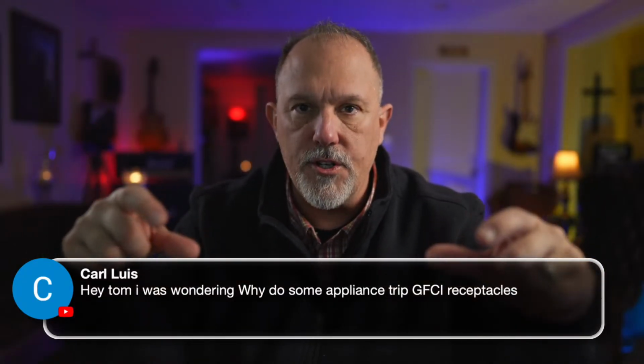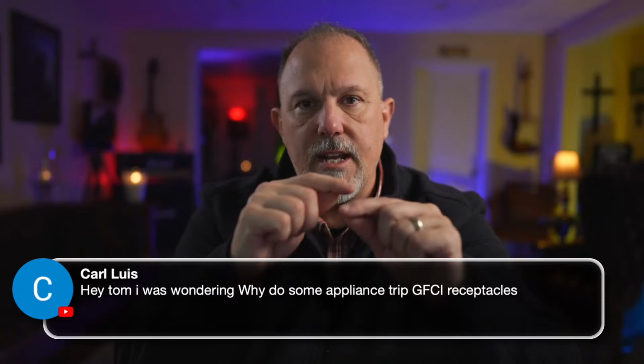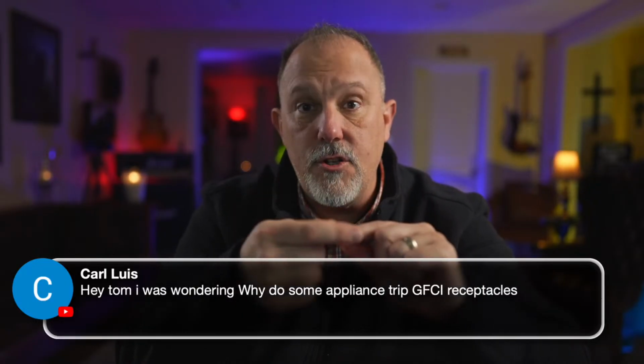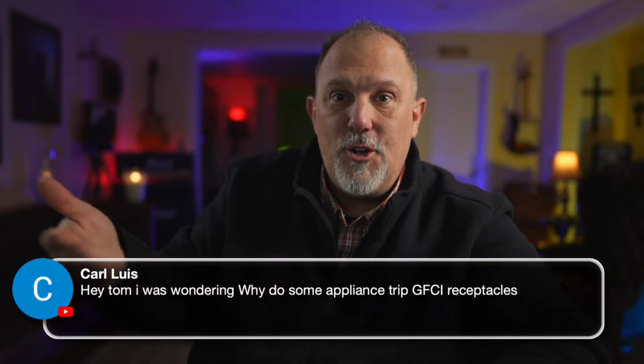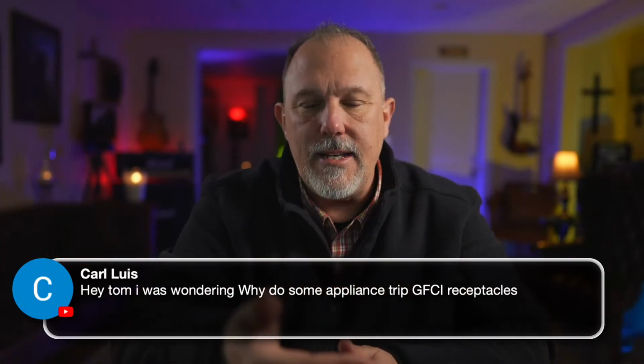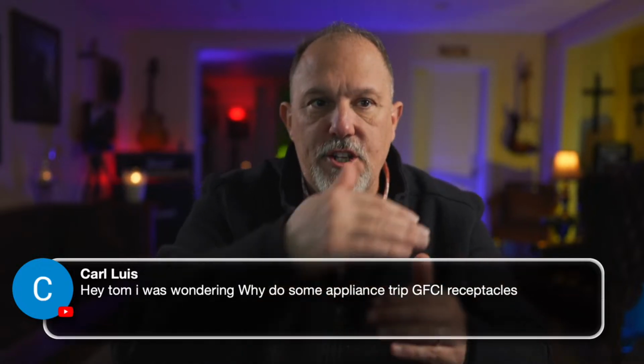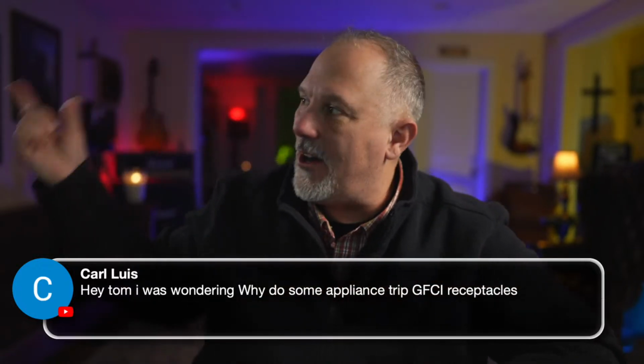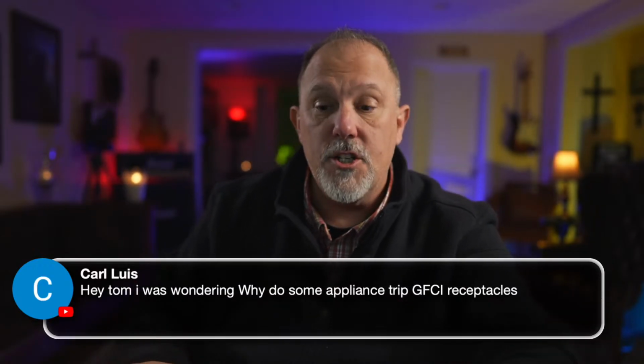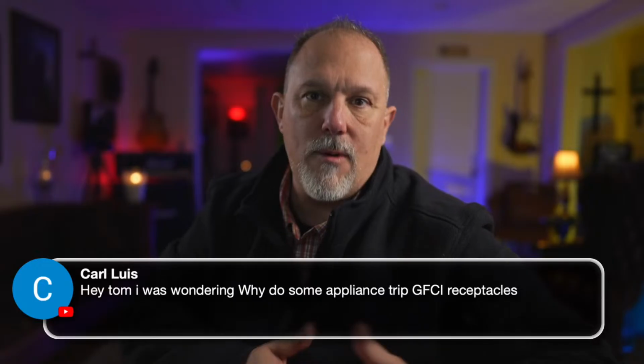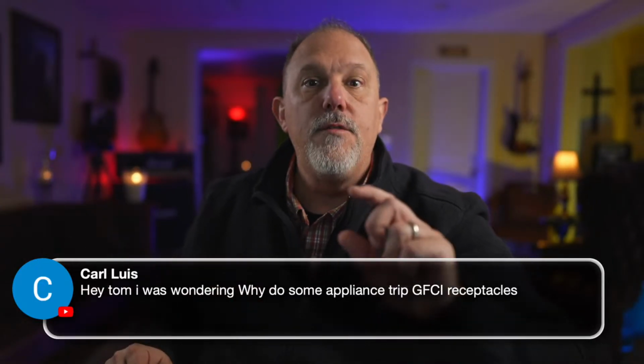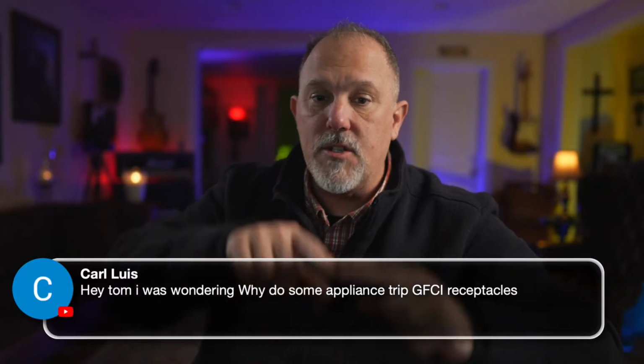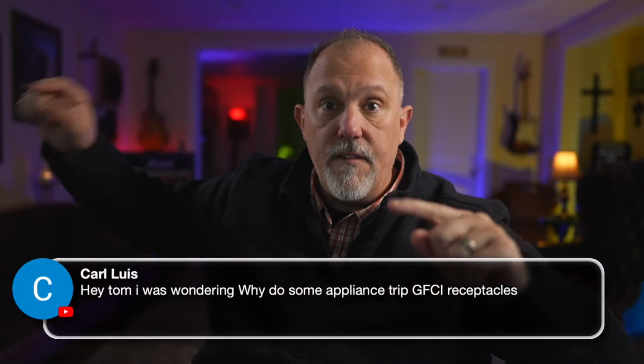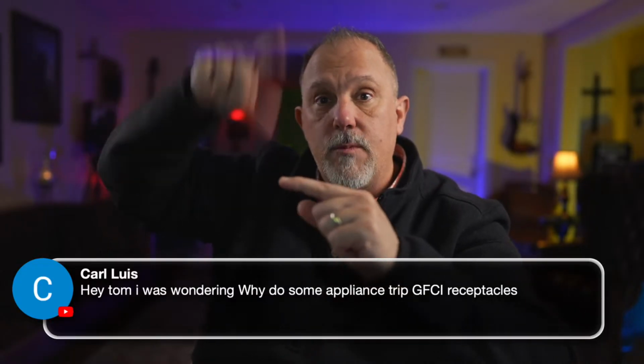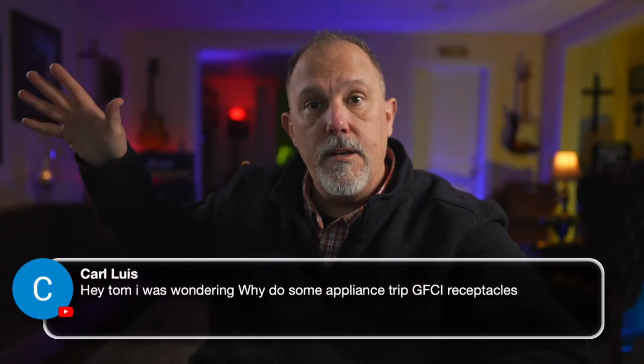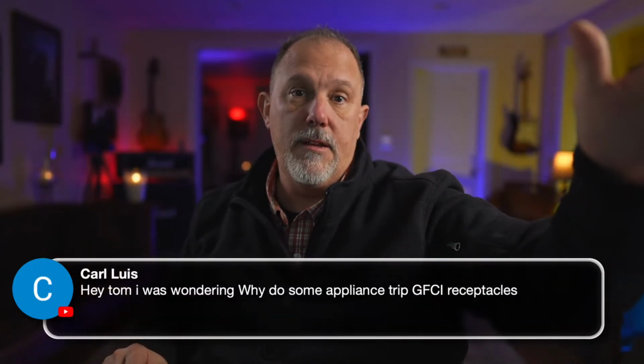They had a power strip, but it was a surge suppressor, and the MOV was connected to the ground instead of the neutral. You have a hot and a neutral. Instead of shunting the currents to neutral, they shunted them to ground, and it would cause the 30 milliamps to trip. So we had to put an intentional delay in that 30 milliamp ground fault circuitry inside the breaker to ride through these blips. We would see the blips when you would have a utility ring wave from capacitor switching. The capacitor would switch, you would have a ring wave, and then boom, the surge device would go off, and boom, the breaker would trip.